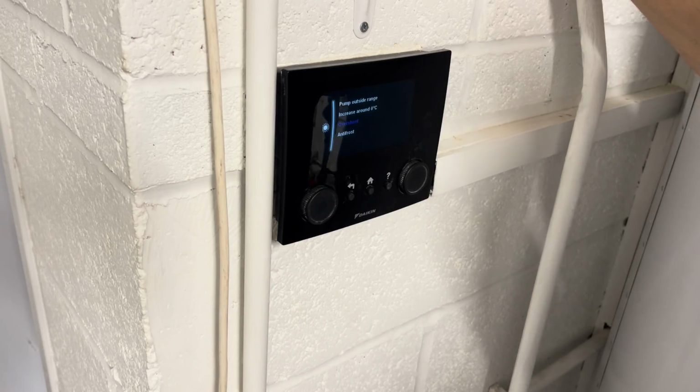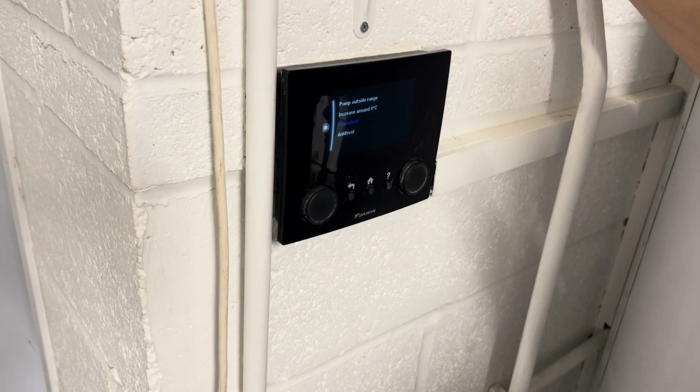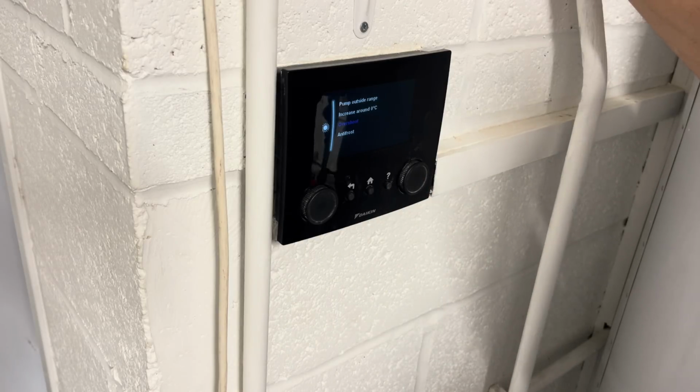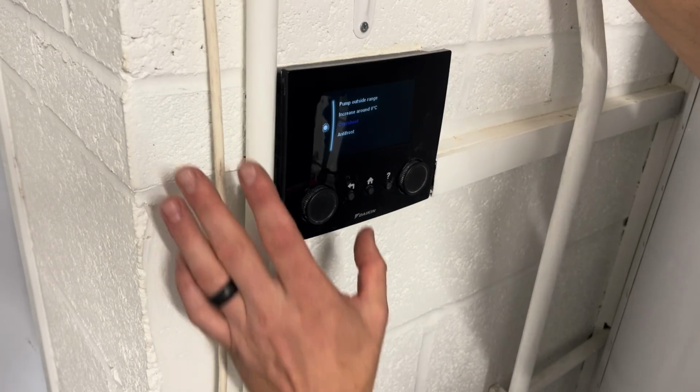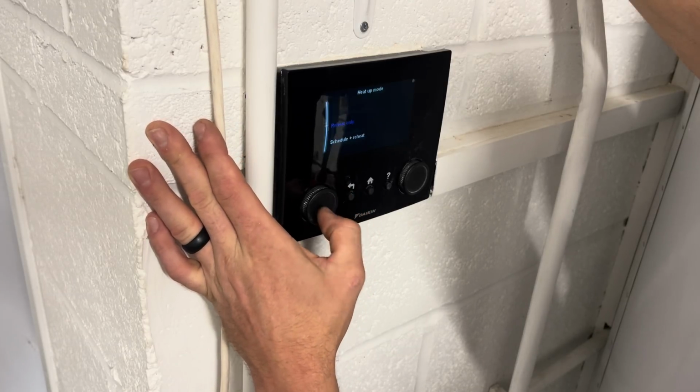So it's overshooting 4 degrees over its target temperature as well. That should be, they should have a 0 on that. But yeah, them 2 things are even on a higher weather curve. They're overshooting on the curve and on the target flow temperature as well. Crikey.